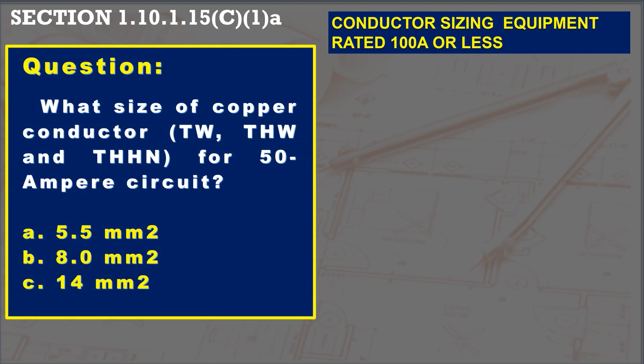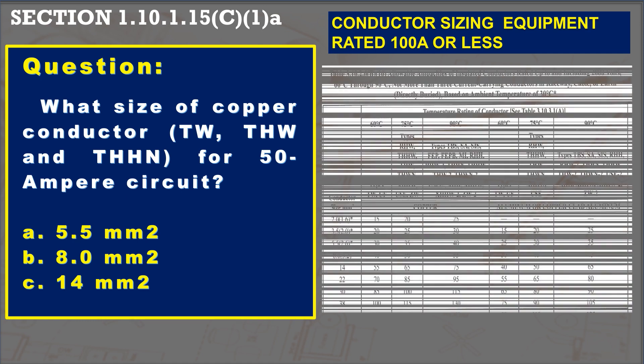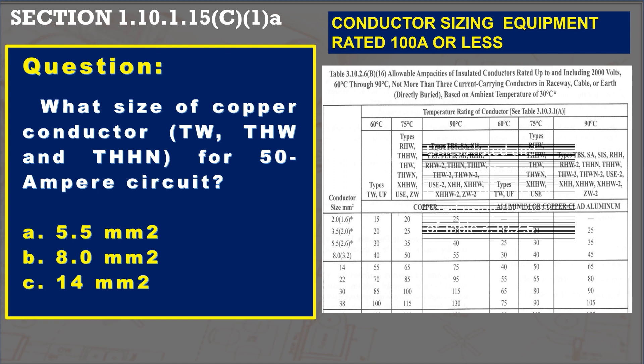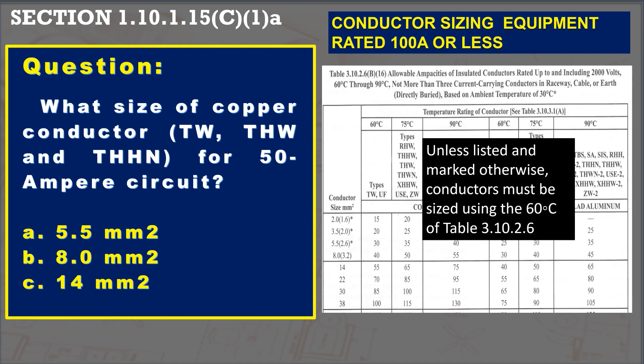In complying with the equipment terminal rating, what size of copper conductor — TW, THW, and THHN — for a 50-ampere circuit? Options are A: 5.5 squared millimeters, B: 8 squared millimeters, and C: 14 squared millimeters. Unless listed and marked otherwise, conductors must be sized using the 60 degrees Celsius column of Table 3.10.2.6. Therefore, 14 squared millimeters is the answer, whether it is TW, THW, or THHN.